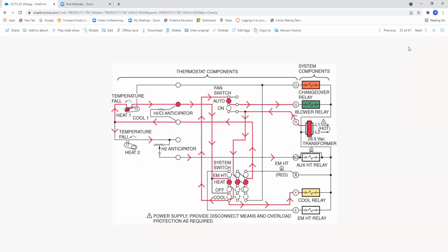I want to call your attention to a couple things. You have 2-stage heating and 2-stage cooling, plus you have an emergency heat position. These represent the various switch actions that the customer can engage, whether it's a manual rocker type switch or a digital switch. And notice that you have different components. The E terminal on this subbase is going to energize the emergency heat relay. Y is going to energize the cool relay. X is basically an indicator light. And what this does, when you energize the emergency heat, you're also going to energize the X terminal, which in turn is going to bring on the emergency heat light, telling the customer, hey, the emergency heat is on. Please pay attention to that.